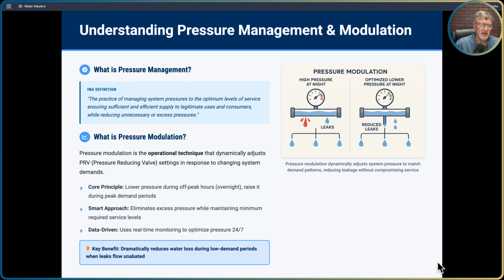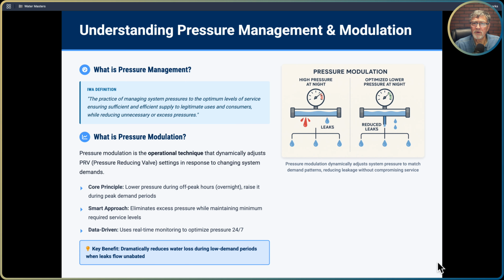So, what is pressure modulation then? Pressure modulation is the operational technique that dynamically adjusts, through the PRV, or the pressure regulation valve, settings in response to changing system demands. We'll look at the different PRV valves out there, but that's going to be your main technique. The core principle is really lower pressure during off-peak hours, so overnight usually, and raise it during peak demand periods, so you're maintaining steady water pressure and not putting that stress on the pipes. Smart approach eliminates excess pressure while maintaining minimum required service levels. And data driven, it uses real time monitoring to optimize pressure 24/7.